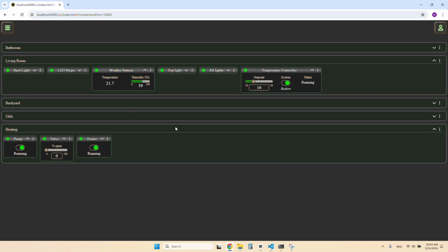It will take some time, so the system is shutting down as it's not needed at the moment. The heater is off, the valve was shut down already. Finally, the circulation pump shuts down and the system status changed to ready. The temperature is still falling. Getting close to the set point. And the system starts up as soon as the temperature falls below. Cool, that's exactly how it was meant to work.